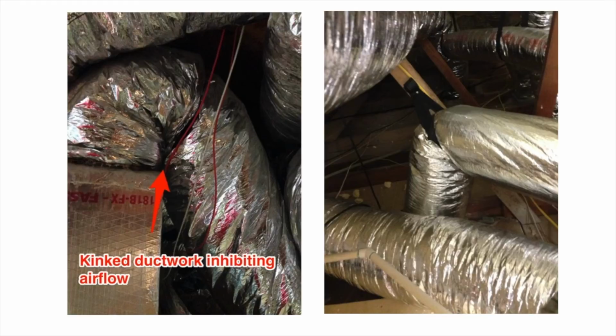Here are some pictures of some kinked ductwork. You can see in the picture on the left, the supply side ductwork coming off of the plenum is making a 180-degree turn immediately to go to another part of the house. This is obviously crimping off some of the airflow that might be going through there. The picture on the right is right above where the duct is going to meet the supply bucket, and this kink could have been mellowed out to make it more of a curve as opposed to a 90-degree angle, and that would definitely help with airflow.